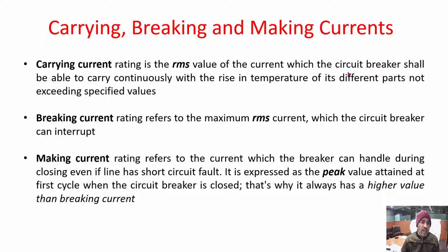What is carrying current? Carrying current rating is the RMS value of the current which the circuit breaker shall be able to carry continuously, with the rise in temperature of its different parts not exceeding specified values. So this is the carrying current rating. Carrying current means the normal operating current. In those conditions, the circuit breaker is not expected to generate abnormal heat, and abnormal temperature rise is not expected in any part of the circuit breaker.